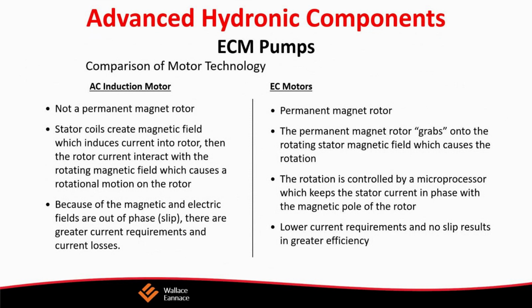But most of what we're focusing on here is smaller buildings and residential buildings as well. And I'd really like to talk about electronic commutated motor pumps, or ECM pumps. If you haven't heard that term, you're certainly going to hear it a lot. This technology uses permanent magnets. There's no shaft, seals, or bushings. The only moving part in this particular case is the spherical impeller or rotor. It's all one unit. There's stepless speed control, and a high efficiency ECM motor.